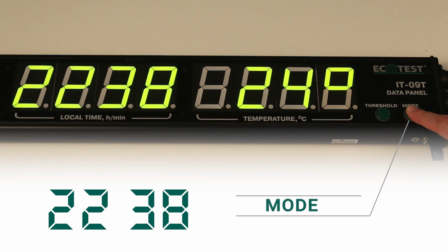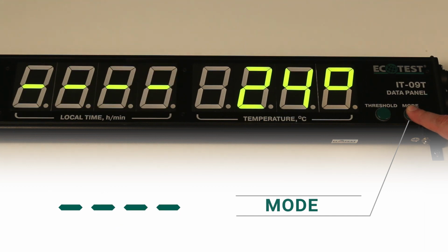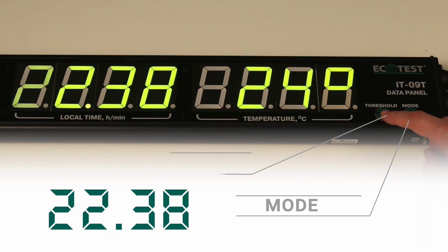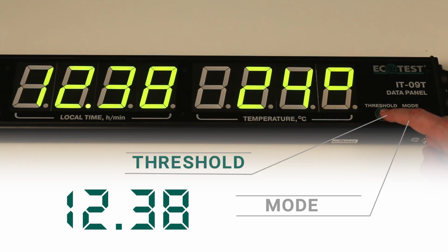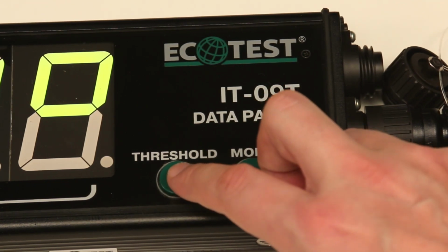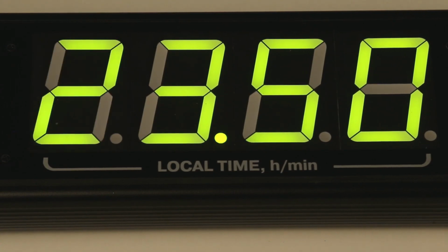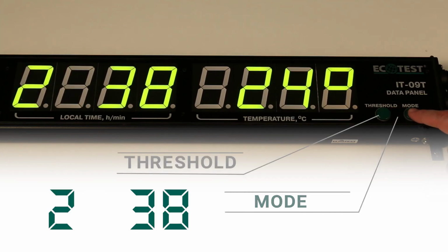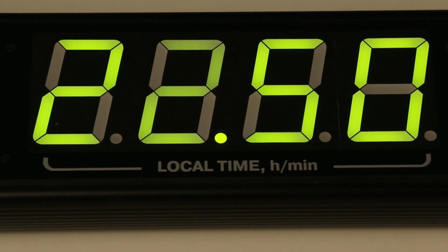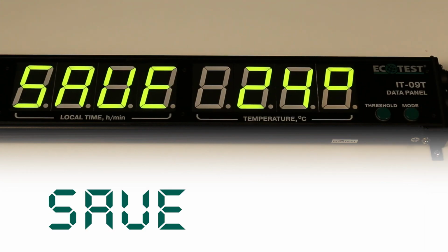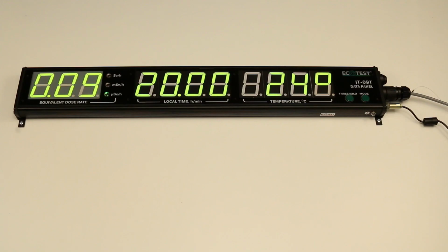Press and hold the mode button till the dotted symbols appear on the real-time indicator. Release the mode button. Change the value of the major digit by shortly pressing the threshold button. To change the value of the next digit, shortly press the mode button and set a necessary value of the digit using threshold button. The values of the remaining digits are changed in the same way. When the last fourth digit of the real-time indicator is changed, this mode is automatically completed. After the symbol Save appears on the time indicator, the panel returns to the mode of indication of gamma radiation dose rate, temperature, and real-time.